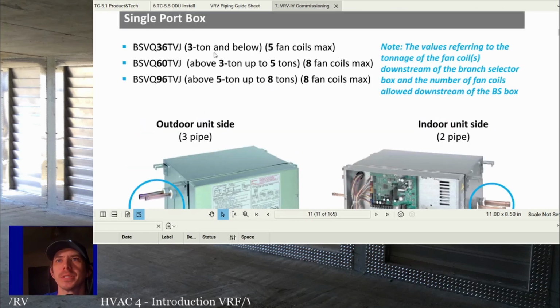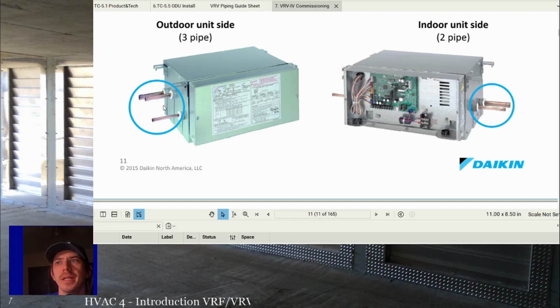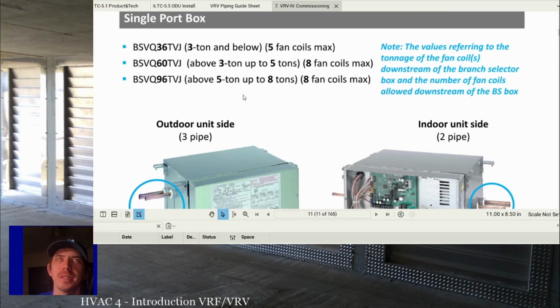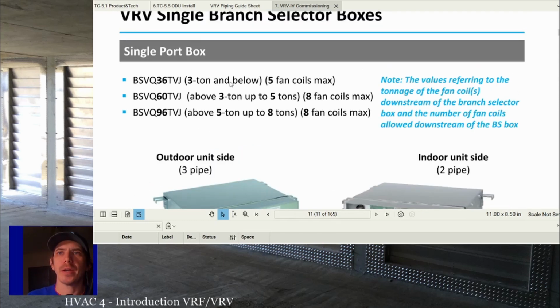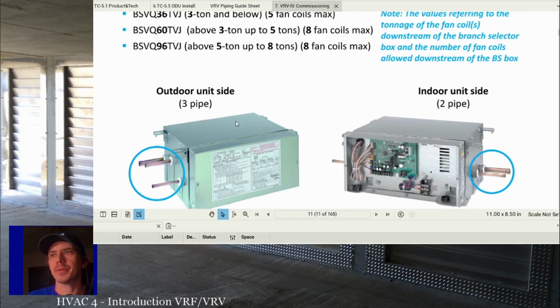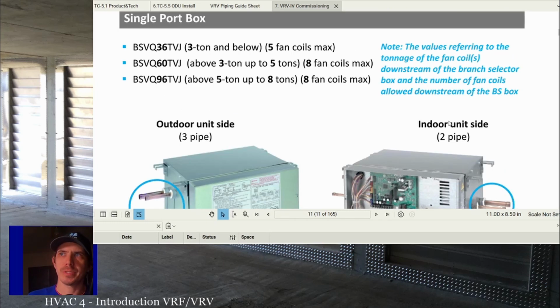So, branch selectors generally come, and this is kind of similar across all manufacturers, in sizes up to 3 tons, 3 tons to 5 tons, and 5 tons to 8 tons. And that's the basics of the sizes. Generally, there's three, maybe four sizes available on branch selector boxes. That may not be the same everywhere, but that seems to be the common thread. So basically, if you have three 1 ton units connected and they're in the same general vicinity, they can be served by one branch selector. The three pipe side is the outdoor unit side because you've got the three pipes coming from the outdoor unit, and the two pipe side is the indoor unit side.